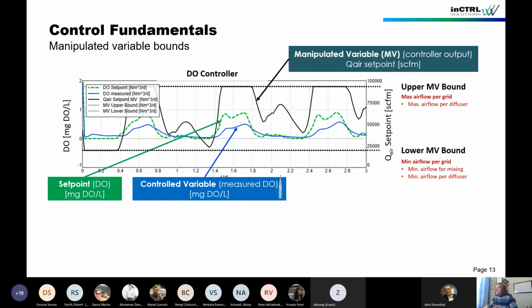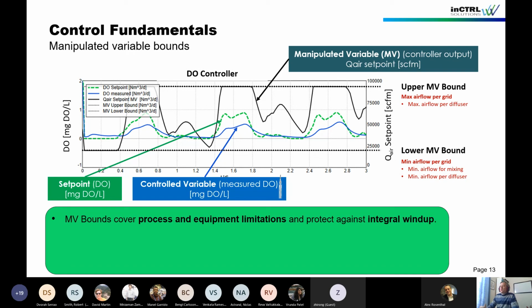So for the lower bound, there are two things. One is minimum airflow for mixing, so that the sludge is not settling. And the other one is minimum airflow per diffuser. That might be very, very critical because ceramic diffusers may actually be damaged if you go below. So very important, that protects your equipment in this case. Good, so just a summary. The manipulated variable bounds cover process and equipment limitations and protect against integral windup. Not enough time today to go into integral windup. Very important topic as well.